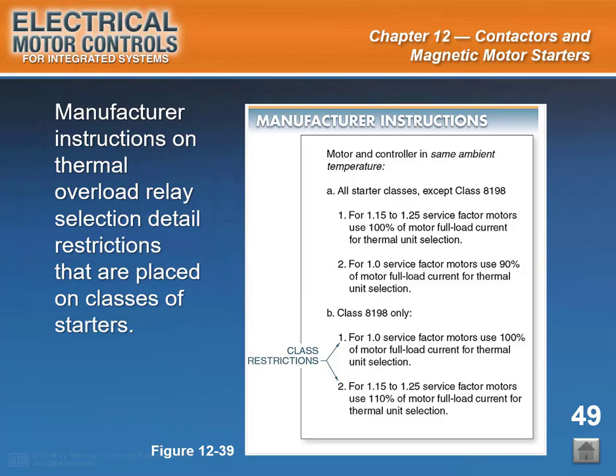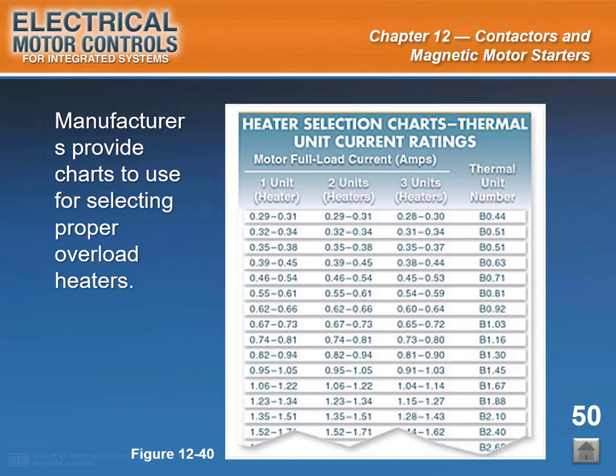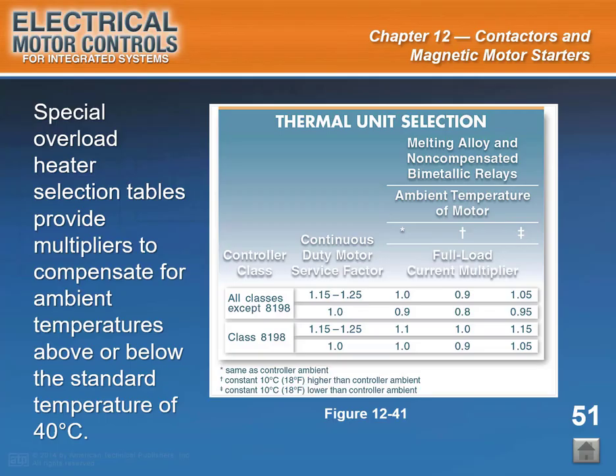End of slide 49. Start of slide 50. Slide caption: manufacturers provide charts to use for selecting proper overload heaters. See figure 12-40. The correct heater selection chart must be used for the appropriate size starter. This information is also found within the enclosure of many motor starters. Each motor starter manufacturer has a chart that applies to their specific brand. End of slide 50.